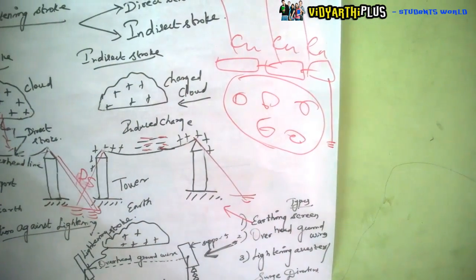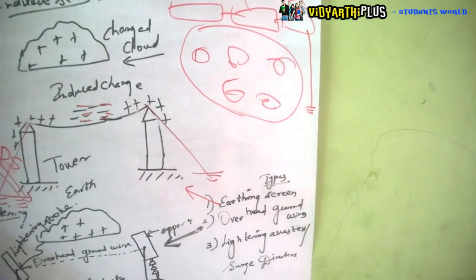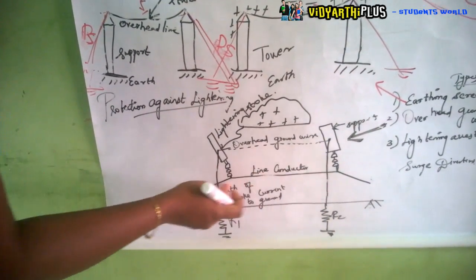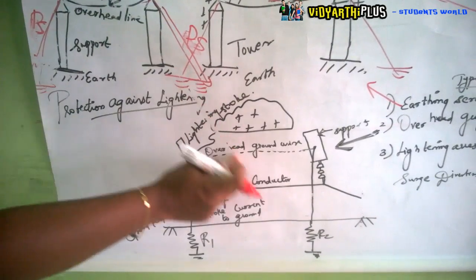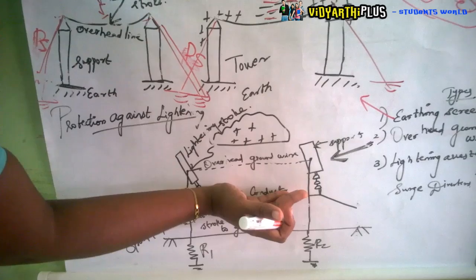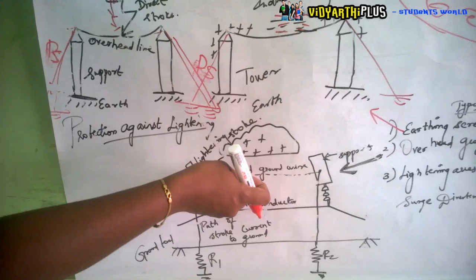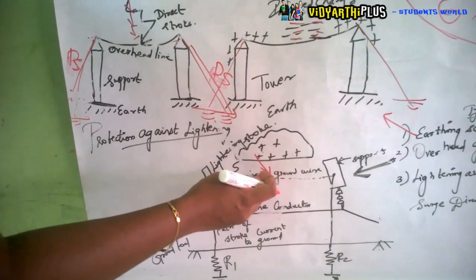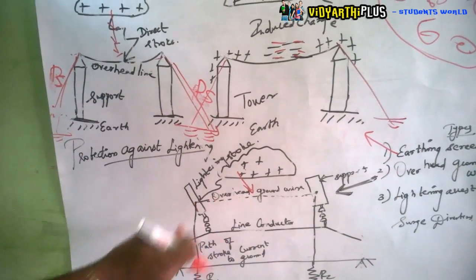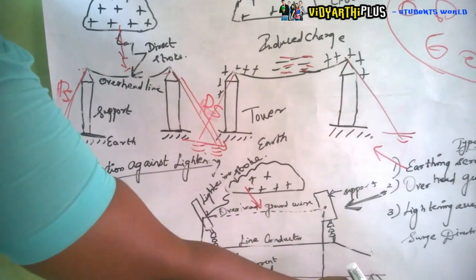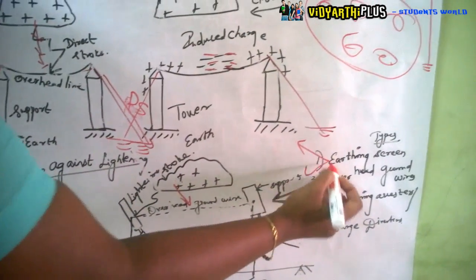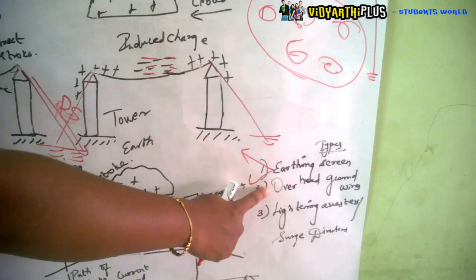The second method is overhead ground wires. A ground wire is placed above the line conductor between two towers. If lightning comes from the cloud, it strikes the overhead ground wire instead of the line conductor. Since the overhead ground wire is connected to ground, the charges are immediately directed to earth without affecting the line conductor. This method protects the transmission line against lightning.